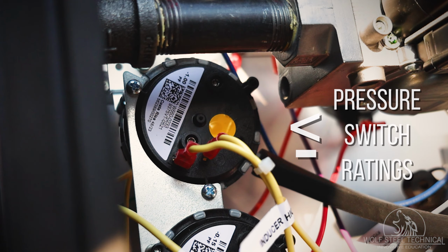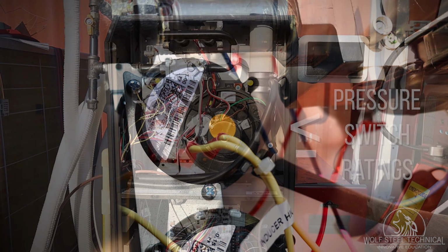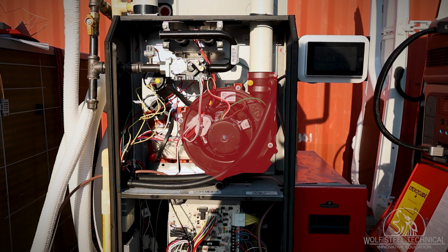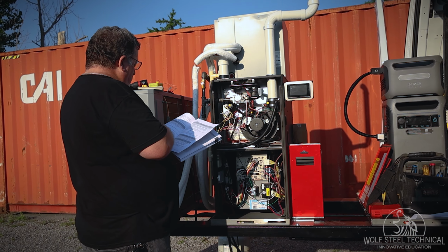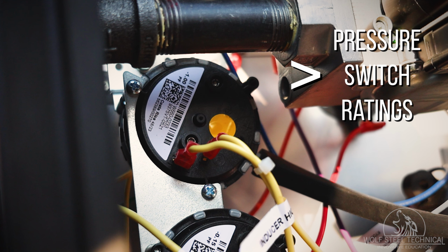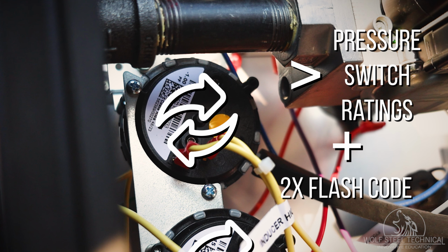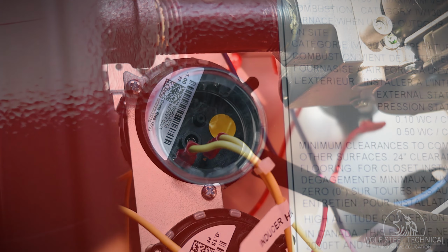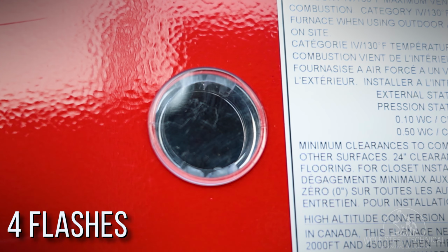If the readings do not exceed the pressure switch ratings, check the operation of the venter motor and ensure the venting and condensate are correct as per the installation and operation manual. If the readings exceed the pressure switch ratings and a 2-flash code is present, the pressure switches will need to be replaced. When observing 4 flashes, this signifies a lockout due to too many ignition attempts.